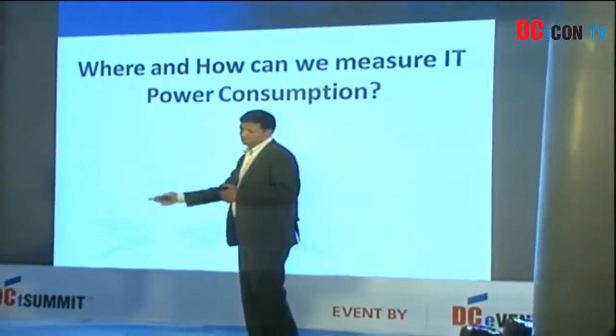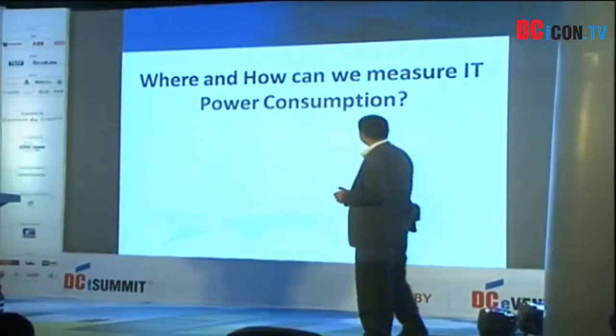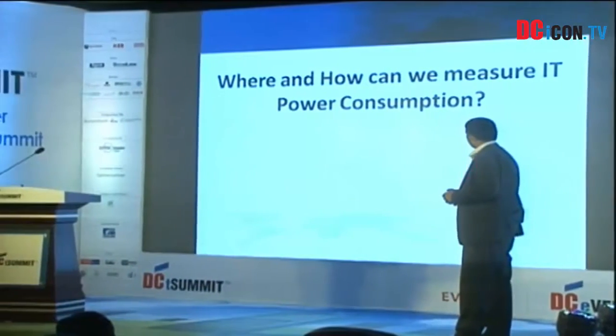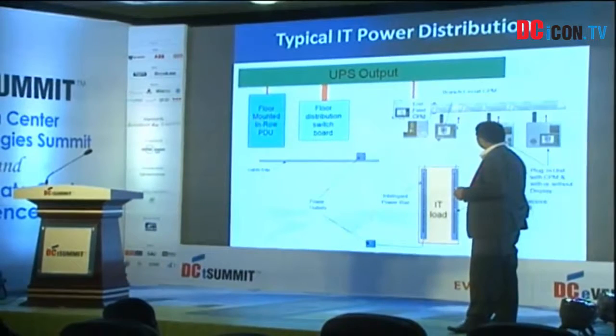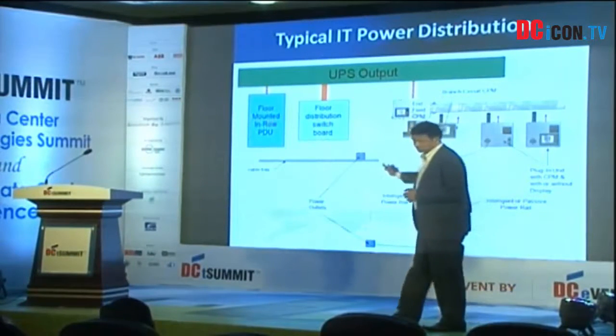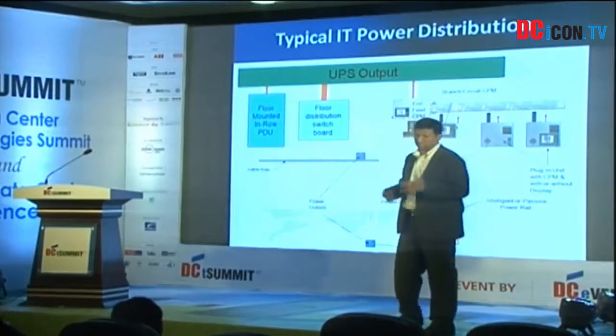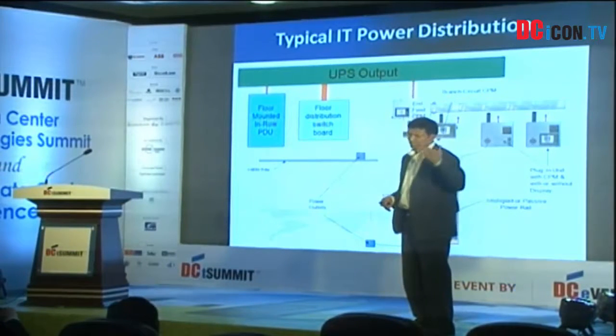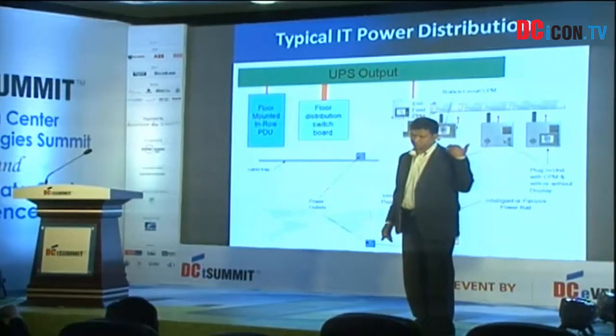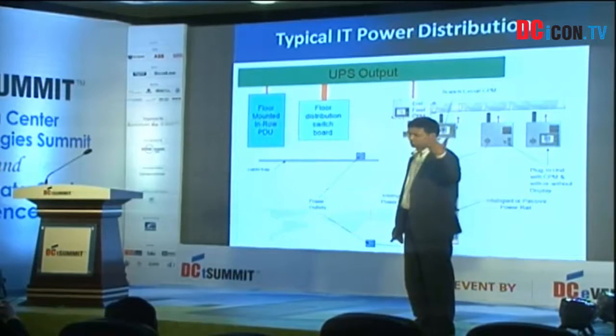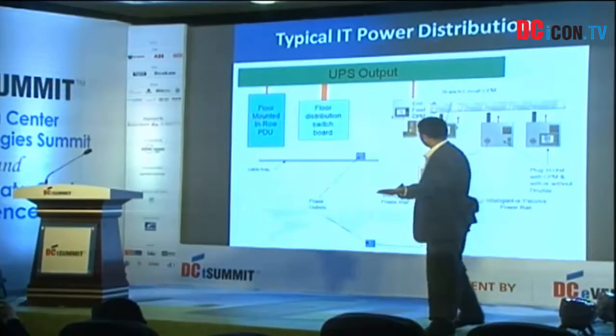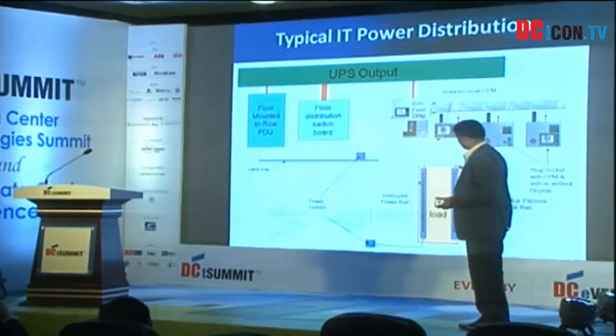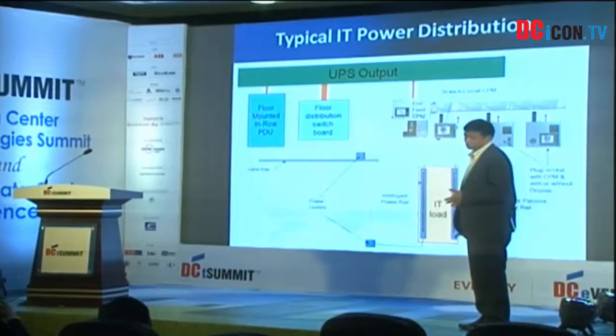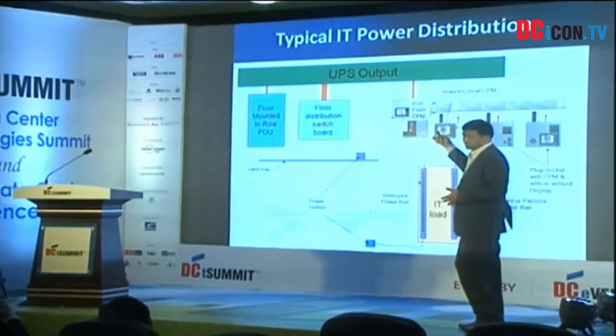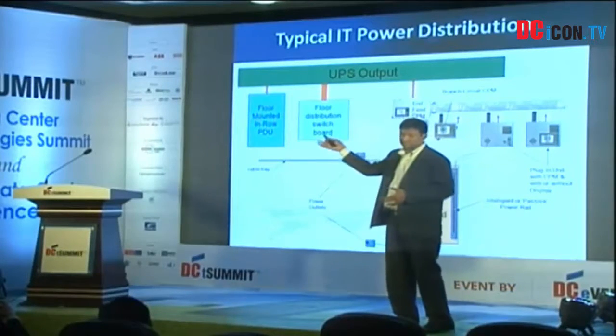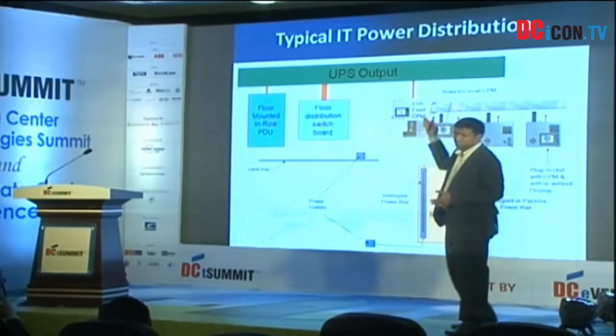So where and how can you measure the IT power consumption? If you look at your architecture within your power distribution, it starts—I'm starting from the UPS point of view. Even prior to that, you have the source of energy coming into your facility, and then your switch gears and various distribution. From the IT perspective, from the data center or critical space perspective, we are starting from the UPS.